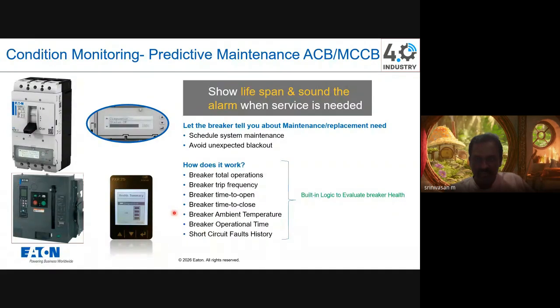We have a kind of watchdog which takes all these activities into account. That means how many times the breaker operated, how many times the breaker has tripped due to short circuit or overload, how much time it is taking to open and close, and what the ambient temperature is around the board. It takes all these activities into account. Then it gives the result in a very simple bar graph format: 25, 50, 75, 100.